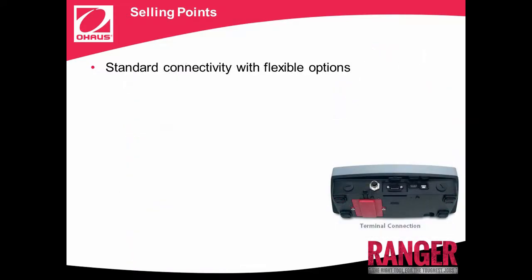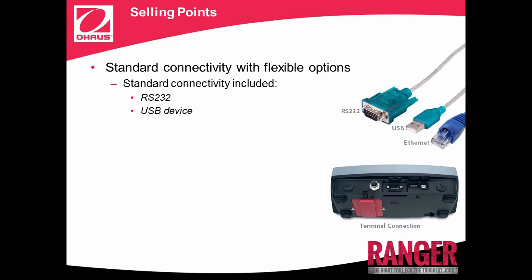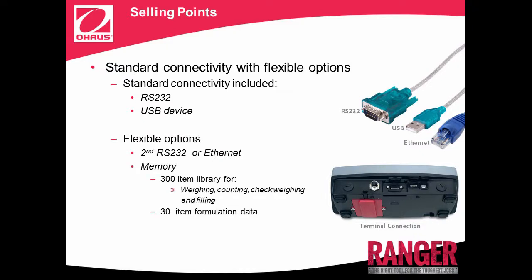Standard connectivity with flexible options. The data produced by Ranger 7000 can be easily exported through the standard connectivity options included: RS-232 and USB device port. Additional connectivity options include a second RS-232 or Ethernet interface. Ranger 7000 contains a 300-item library for storage of weighing data for weighing, counting, check weighing, and filling mode, and a 30-item library for formulation mode, ensuring abundant space for all data storage needs.